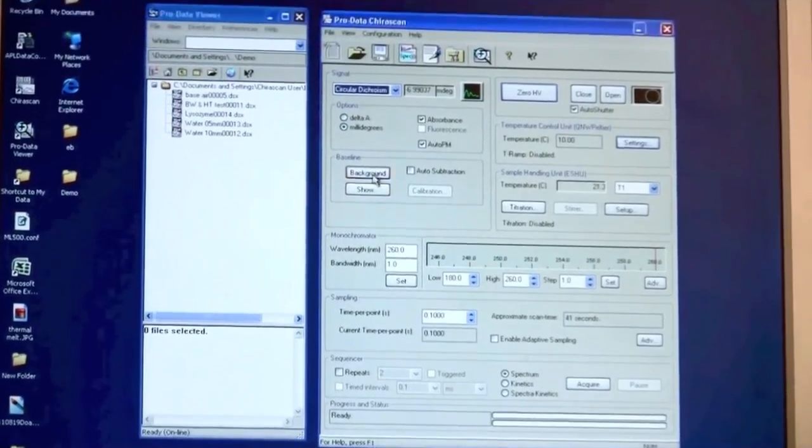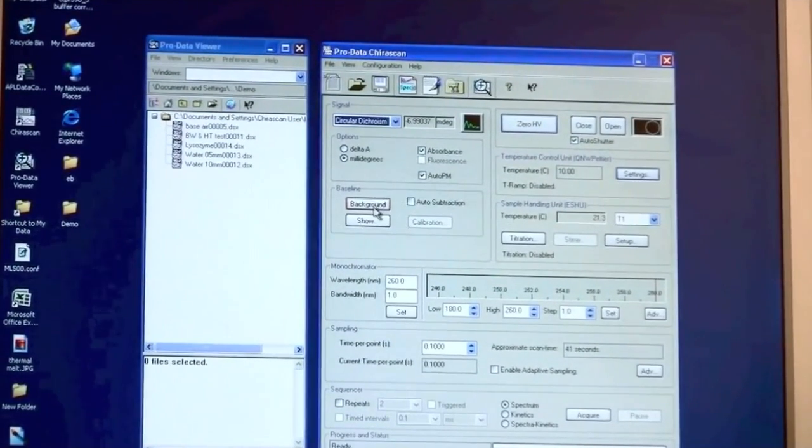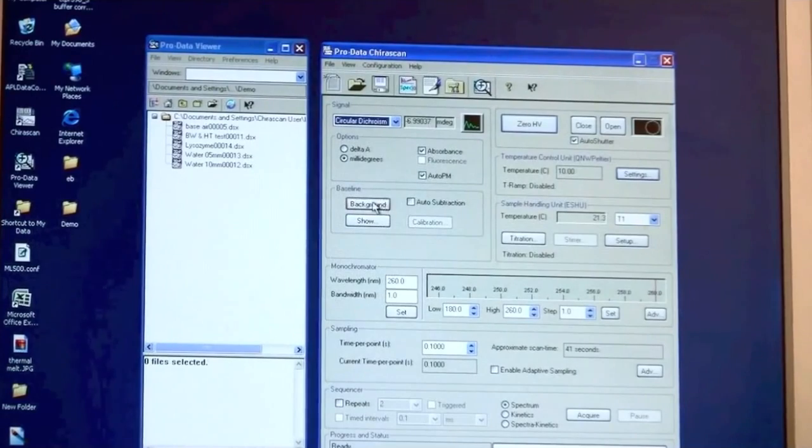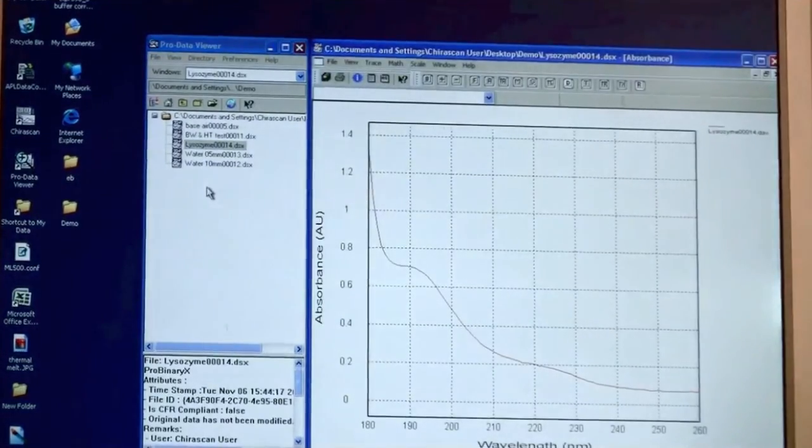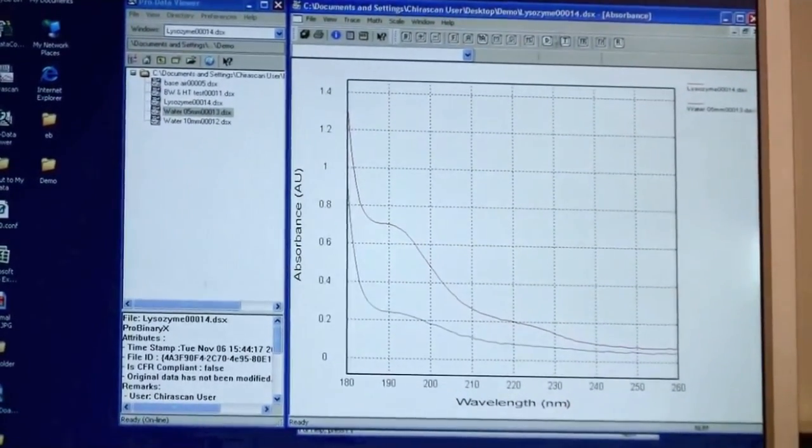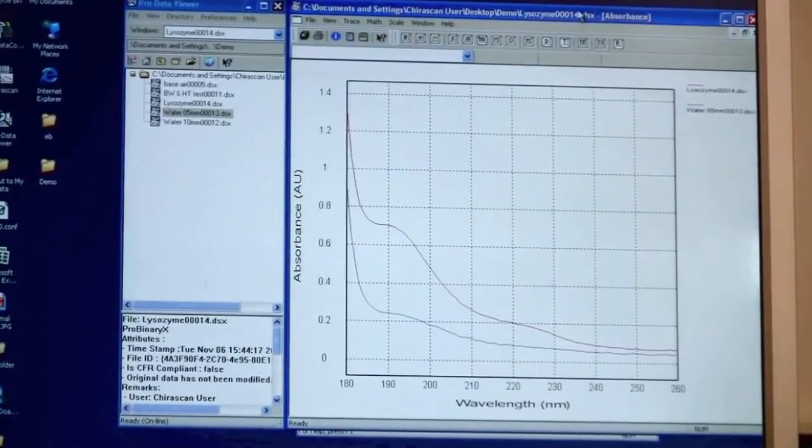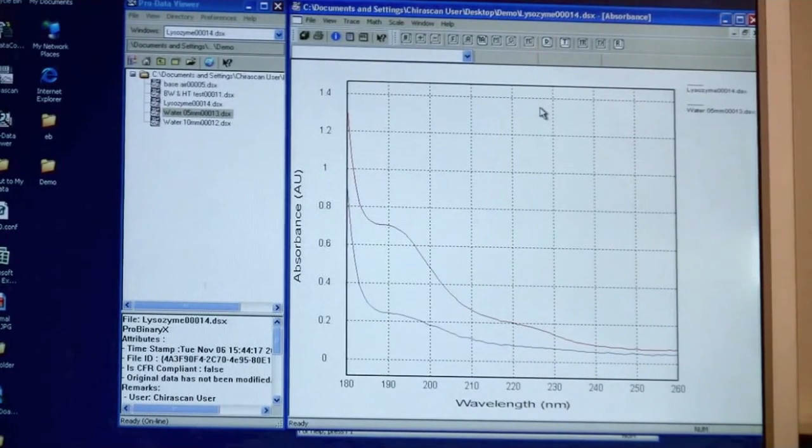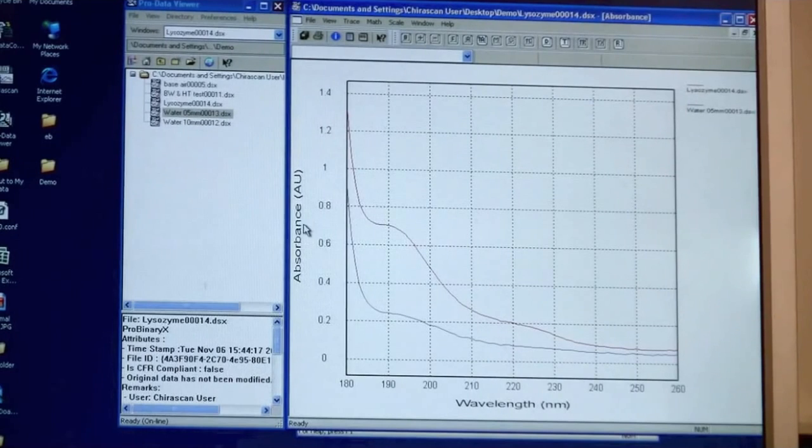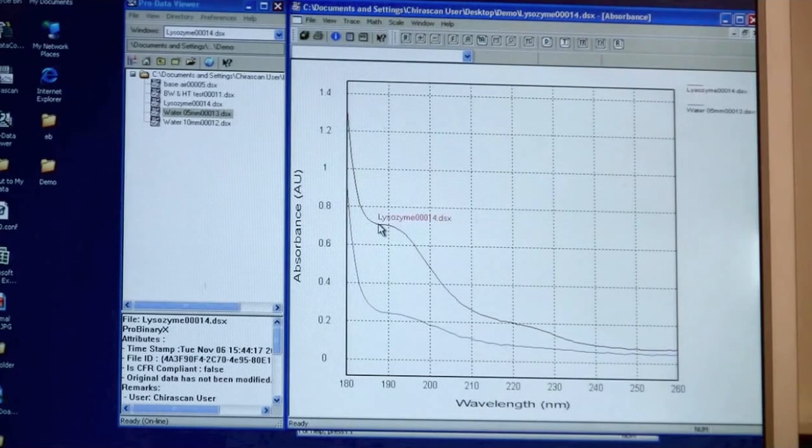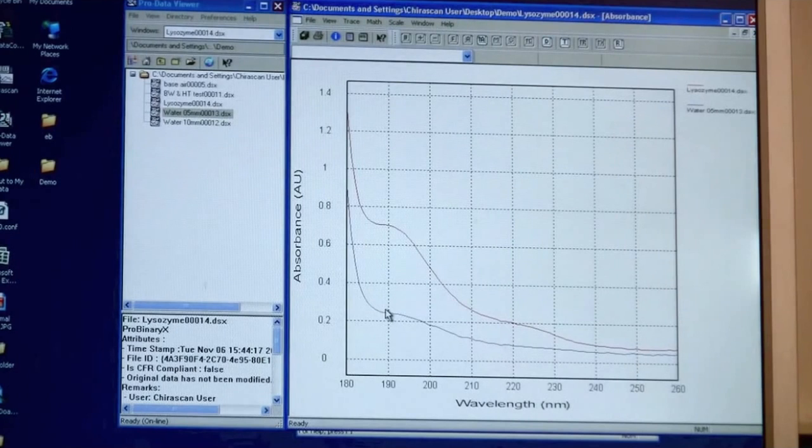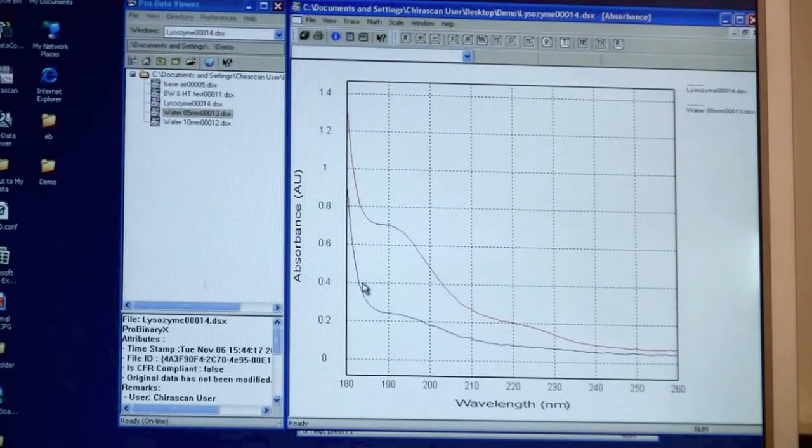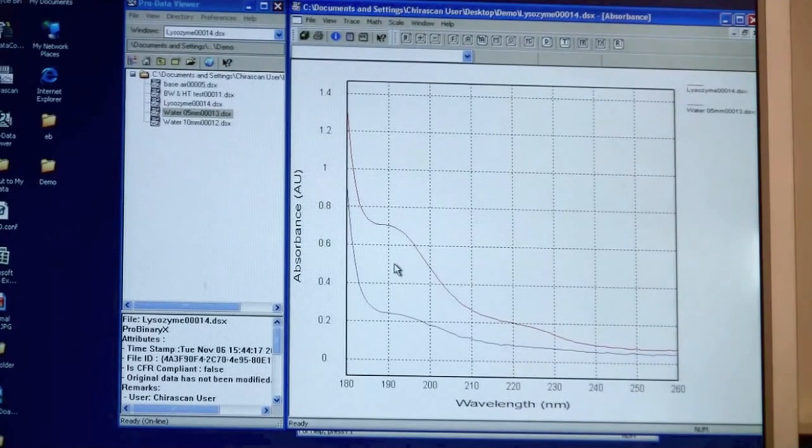So once I have done that, as I have pre-done, this is what it will look like. My lysozyme sample and my water sample. So this is still not in a CD mode. This is in absorbance mode or looking at the absorbance. What I am looking at here is to gain a good difference between the red trace which is my lysozyme sample and the blue trace which is my buffer. Sometimes you experience that the buffer absorbs a lot and it might be advantageous to increase your concentration of your sample to make a bigger difference.